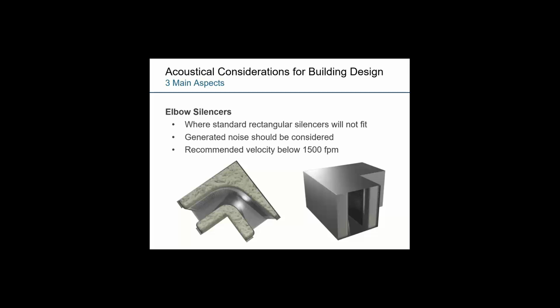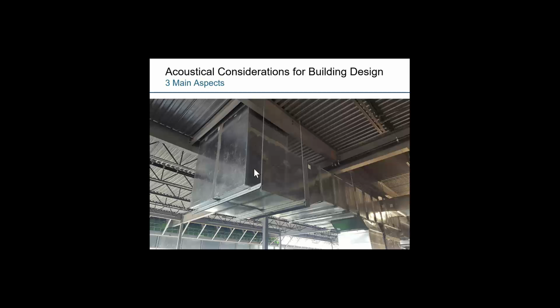Another style of silencer is an elbow silencer. Elbow silencers have typically a 90-degree turn within them, where that sound energy can now be absorbed within the baffles, but the air can also be turned in that same element. To give you an example of an elbow in a practical application would be something like this here, where maybe there is not space to use a traditional straight through or rectangular silencer. An elbow silencer could work well for that purpose, where it's now dropping down through the roof deck and then turning 90 degrees throughout the rest of the duct system.